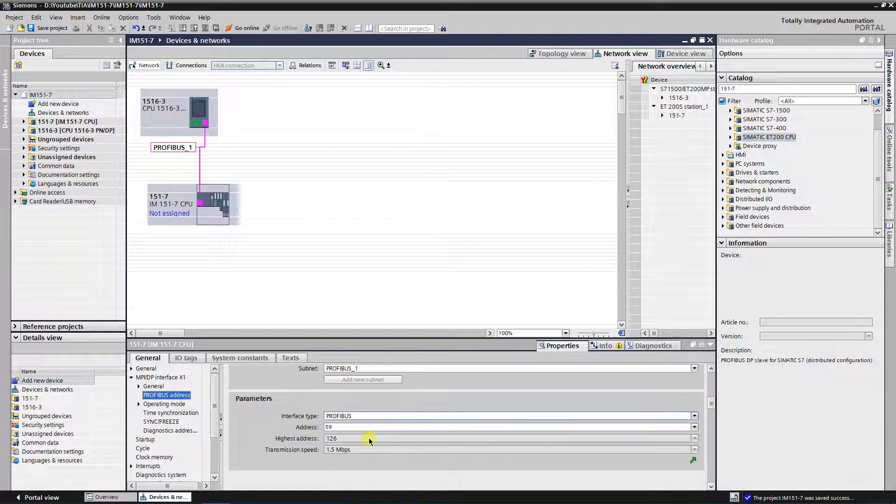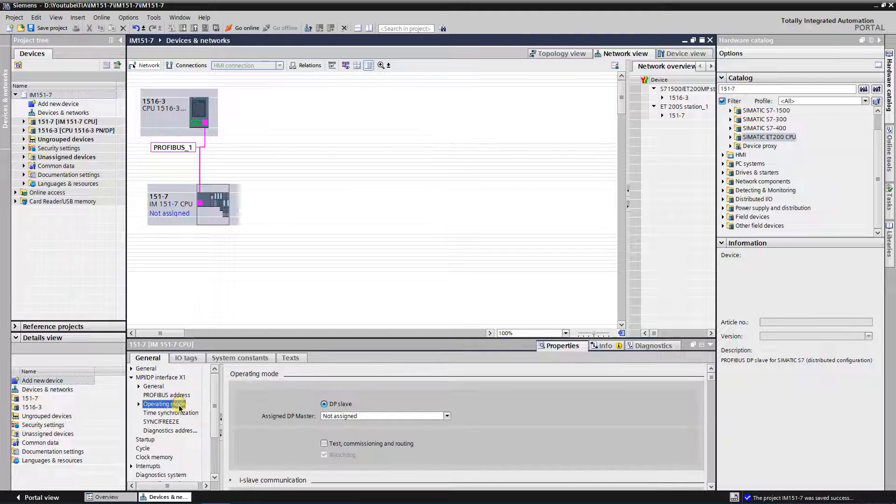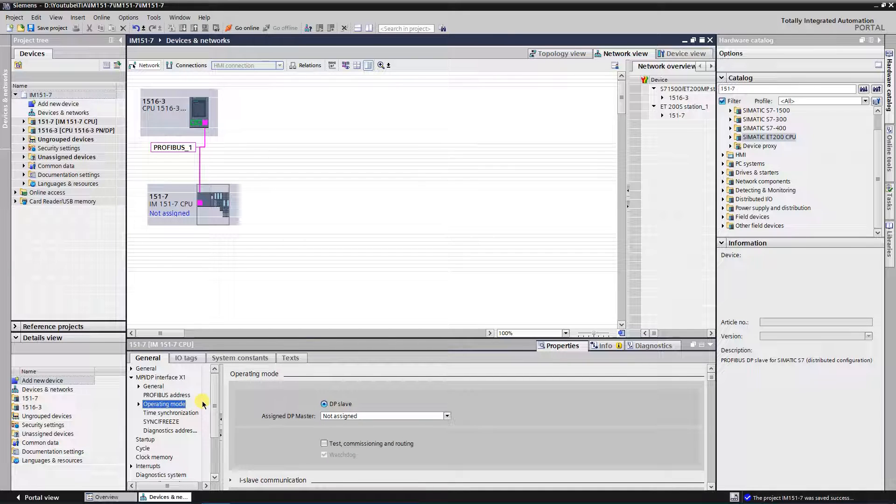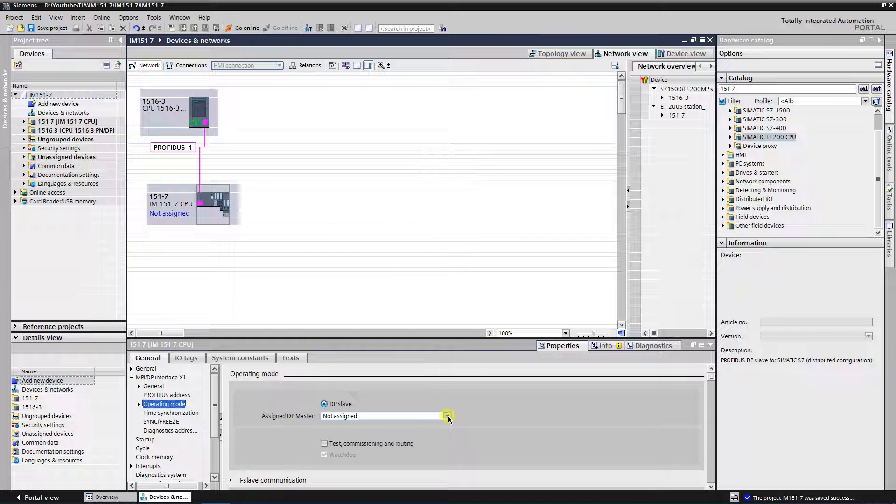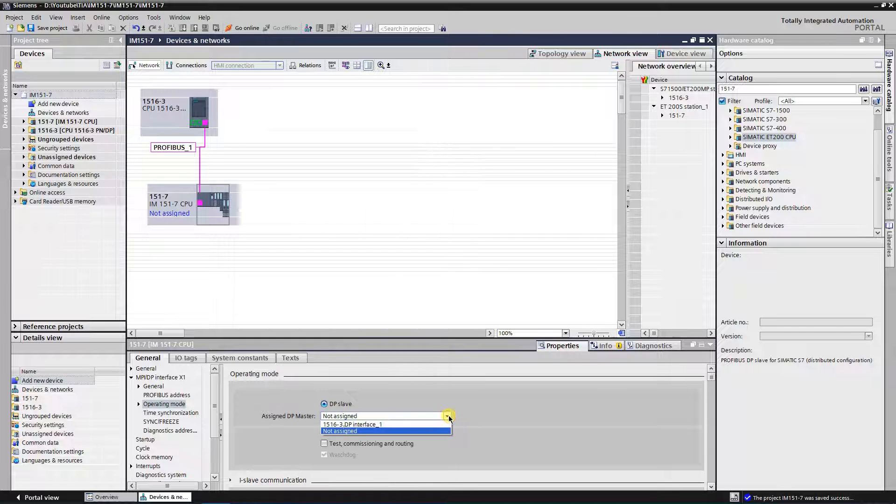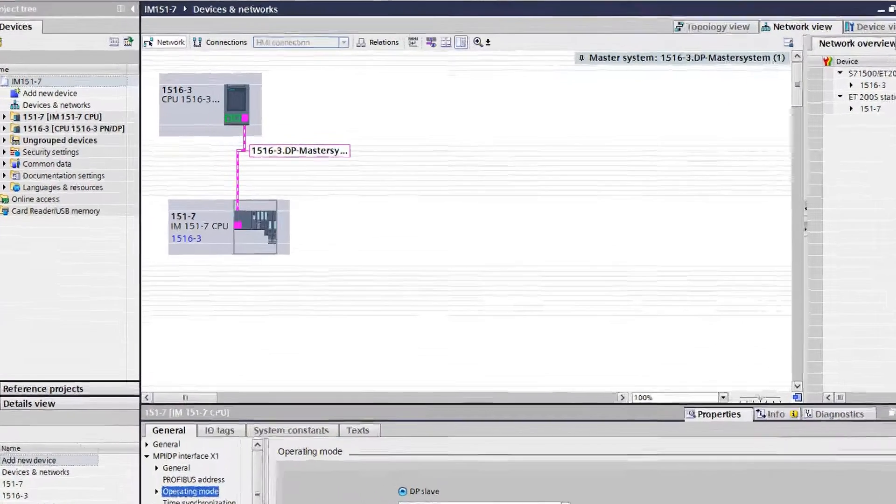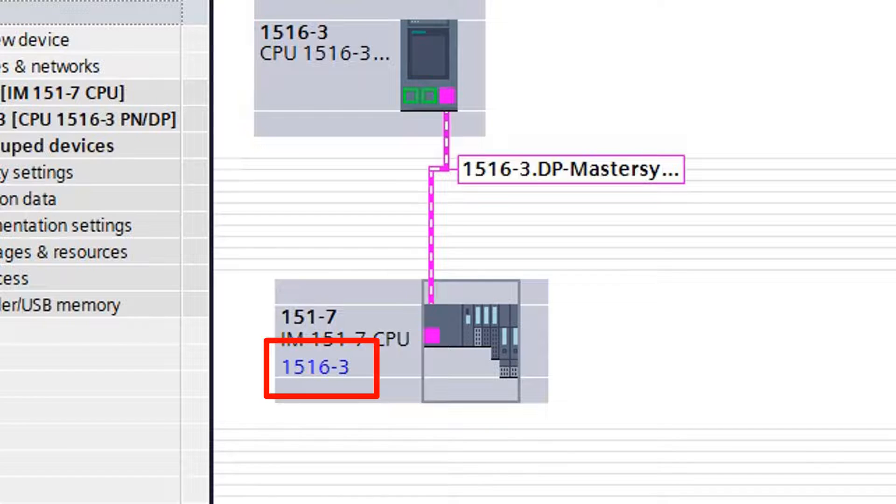To fix that, click on operating mode under the General tab in the properties of the IM 151-7 CPU. Here you can assign a master to your slave. Select DP interface of 1516 CPU from drop down list. Now CPU 1516 is assigned as master for IM 151-7 CPU.